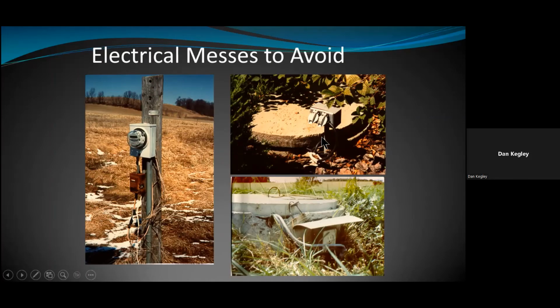Another thing to note on the top right here, they have the rainproof covers for this double receptacle in the top right picture. The state of Wisconsin has adopted that you have to have an in-use cover installed on all outdoor receptacles. So if you're going to install a receptacle outdoors, it has to have an in-use cover, which is a bubble cover, as a kind of terminology we use. So it has to be a hard use bubble cover or in-use cover. It can be plastic or metal. They make several different brands, but you're not allowed to use these rainproof covers anymore. So 316 does require the in-use cover to be installed.